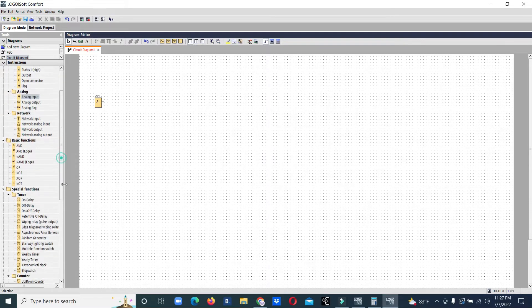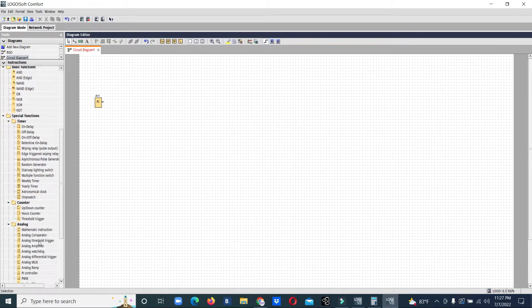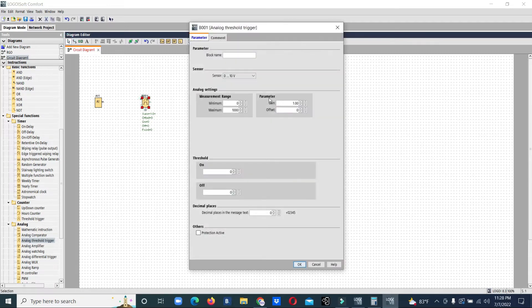Now we will scale our analog value and use analog threshold triggers. We will use three stages of pressure. At zero bar, all pumps will start together. At 4 bar, one pump will stop. At 12 bar, another one will stop. At 18 bar, all pumps will stop. Our pressure transducer is 4 to 20 milliampere, and we keep our range at 0 to 20 bar, scaled as 0 to 2000. So 4 bar corresponds to a value of 400.